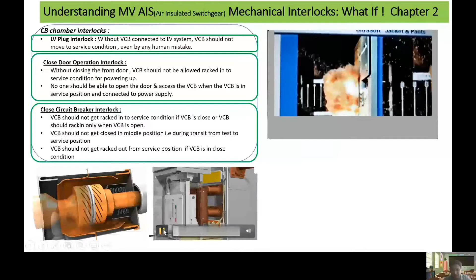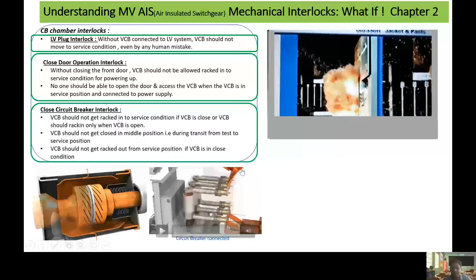And then we have another contact, which is the moving contact and the fixed contact. So if you see, when the breaker is racked inside, then the moving contact gets connected with the fixed contact of the cubicle, or you can say with the power circuit. Along with understanding these contacts, one more concept we should know is that the insulation we are using in switchgear is air, and air is not a very good insulator. So if the distance between the conductor to ground is not adequate, the air will get ionized and there will be internal arc.